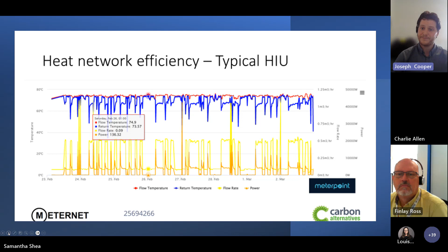So this was just a graph of a typical HIU performance within the apartments then. Again, using the software called MeterPoint, and with our consultant that we've been working with, Carbon Alternatives and Meternet. What this graph essentially is showing is that the flow temperatures are fairly high, but the return temperatures aren't much different. So there's not really any delta T between the flow and the return temperature, which makes it an extremely inefficient HIU in terms of extracting heat within the apartments, but also the effect that has on the boilers in the plant room as they're operating, like I said, on full tilt and consuming a lot more electricity costs than they need to be if there were some controls implemented on them.